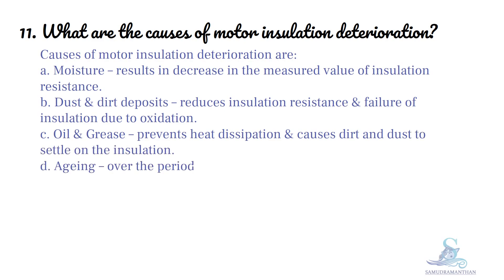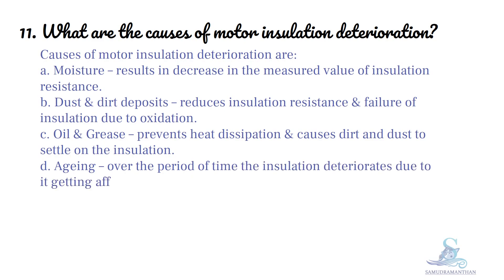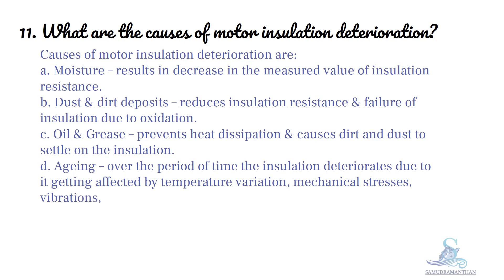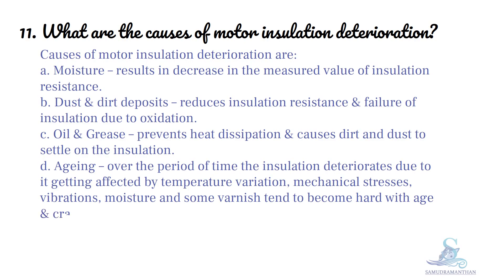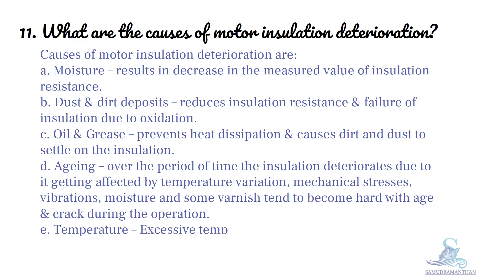Aging: Over a period of time, the insulation deteriorates due to temperature variation. Mechanical stresses, vibrations, and moisture cause the insulation to become hard with age and crack during operation.